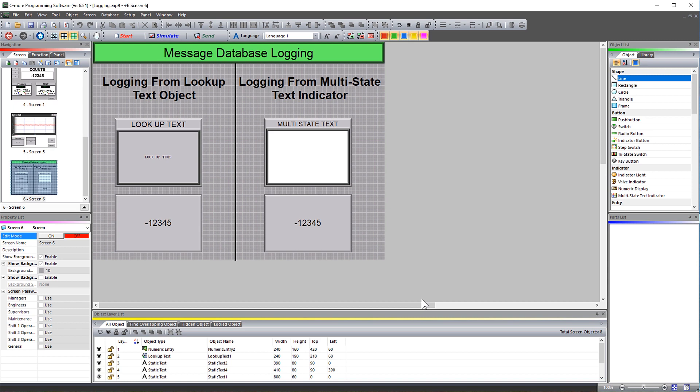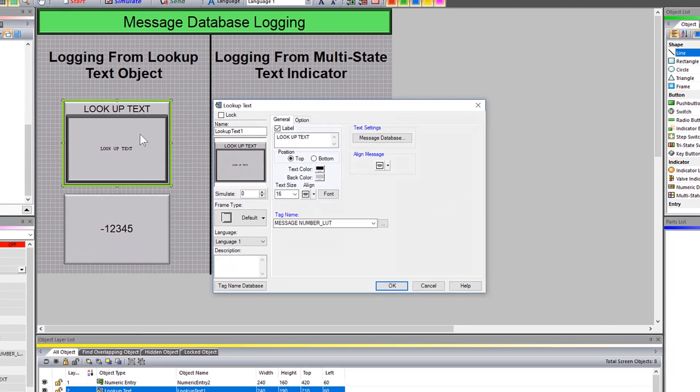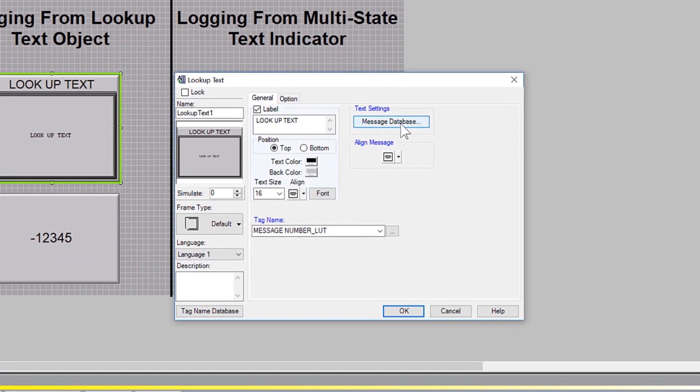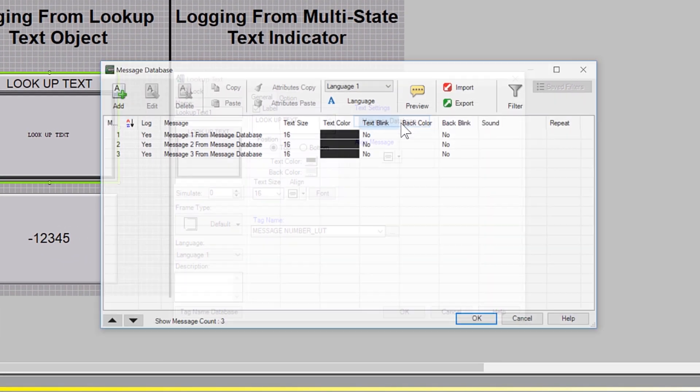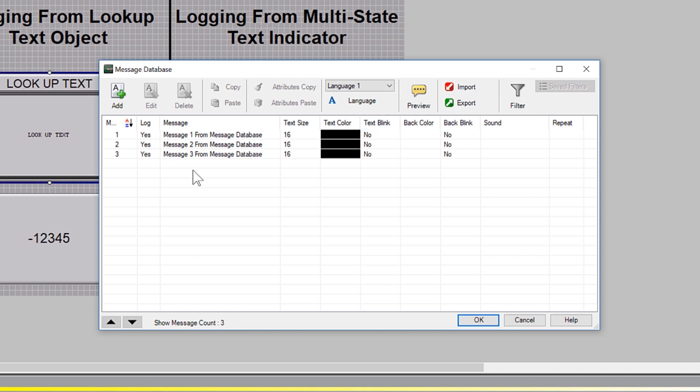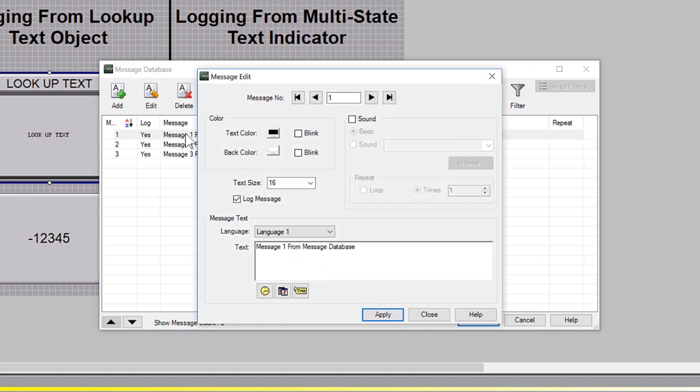With the Lookup Text Object, the message list used for this object comes from the message database here. Any message that is displayed using the Lookup Text Object and has this function selected will have that message logged to the message database log file.